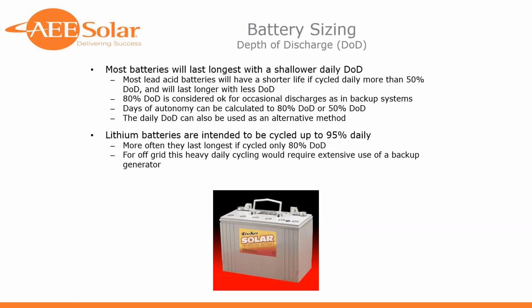I think, again, because lithium batteries can cycle up to 95% daily and are much more tolerant of being at a partial state of charge, the applications are more geared towards multiple cycles and less so around one consistent profile every day where you're charging them down to the same rate every day. Much more geared around self-supply, self-consumption, where we maybe don't know what the discharge is going to be that day. We know that the battery is available. Much more like that than it would be in an off-grid scenario where you've got a pretty good idea of what you're going to use, what your daily needs and your daily rhythms are going to be.